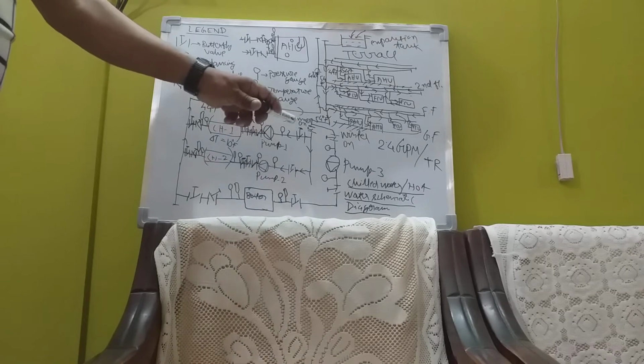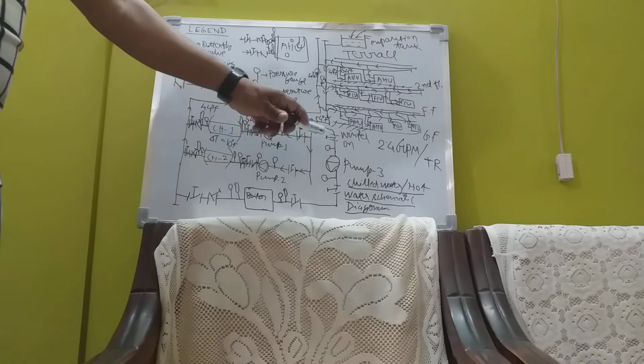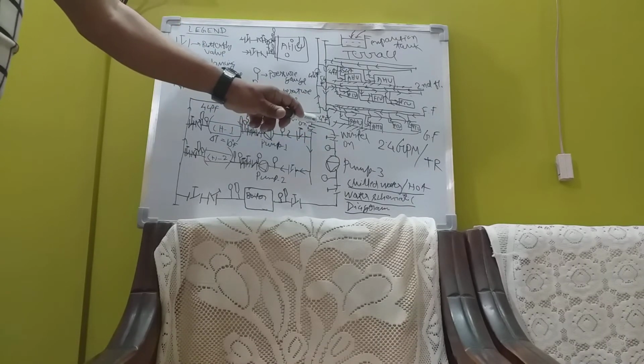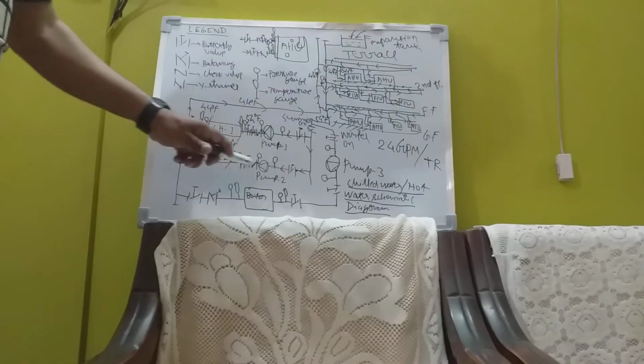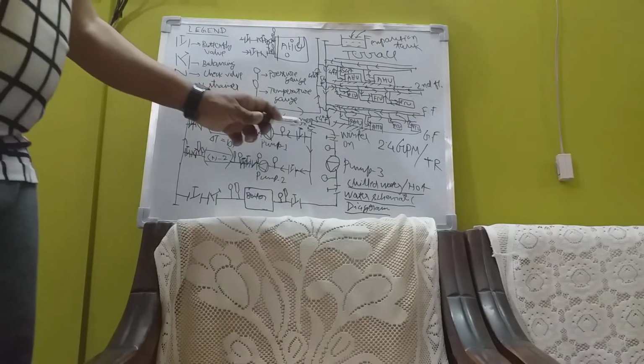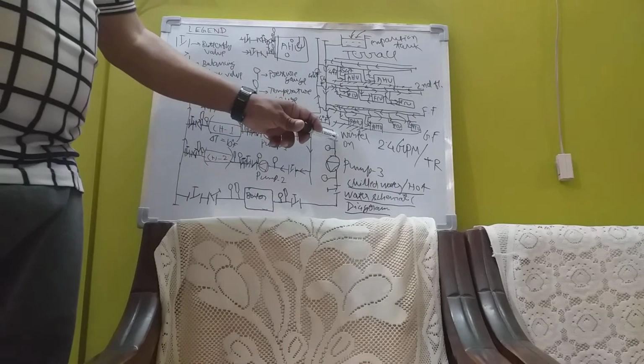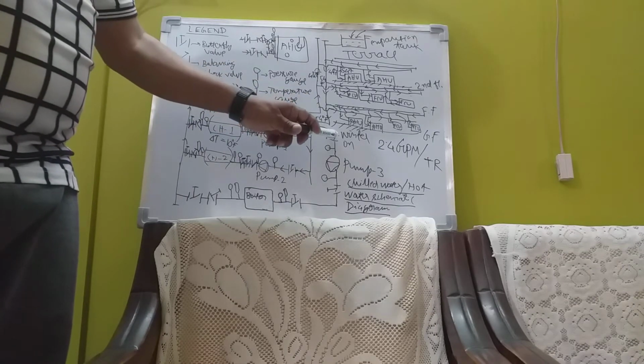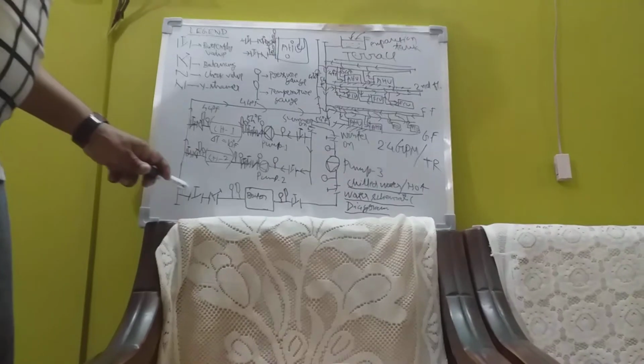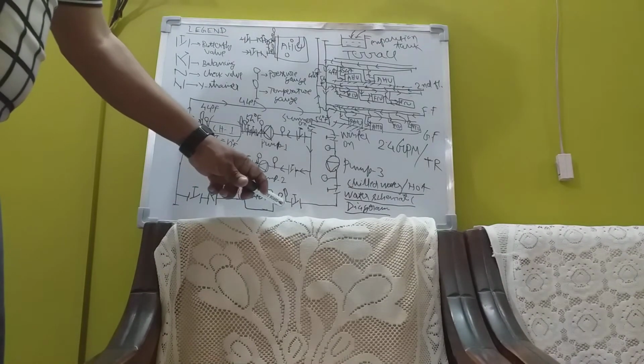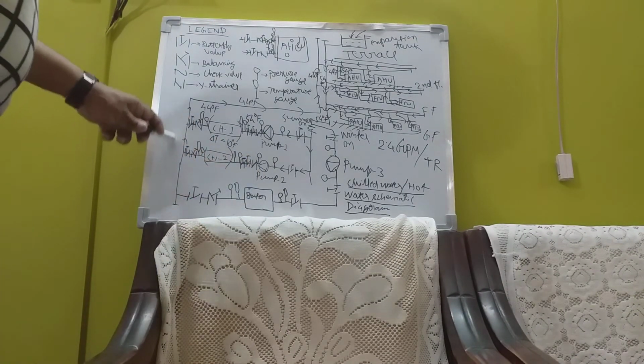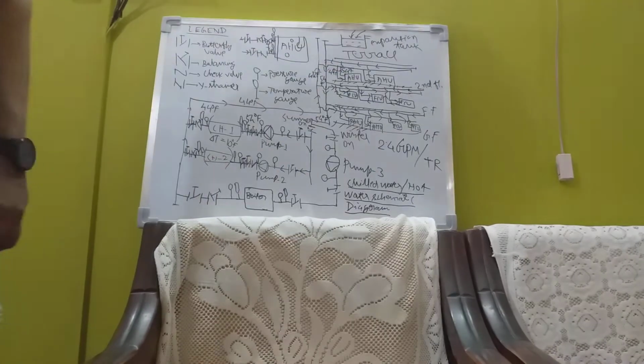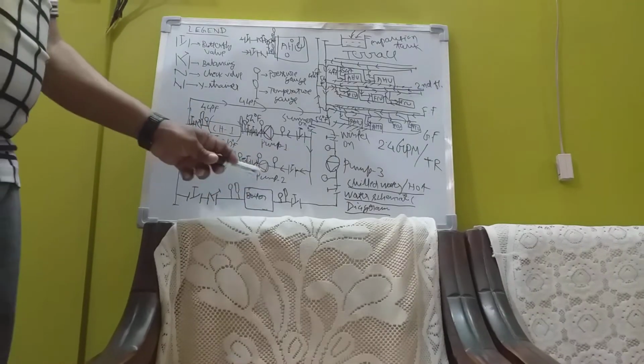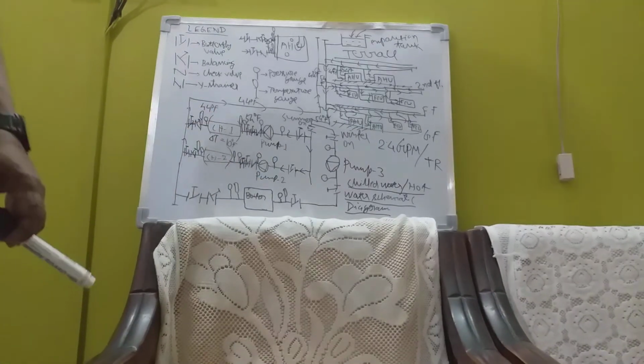During summer, again I am repeating, I put this valve on, put this valve off. With the valve on, water will pass through the chilled water system during summer. During winter, I close this valve, open this valve. Water will come back, come here, pass through this pipeline to the boiler, and in the boiler, there is a rise in temperature of delta T, and from there, water will pass through that system. The rise in temperature depends on the boiler manufacturer, as per the specification given by you.